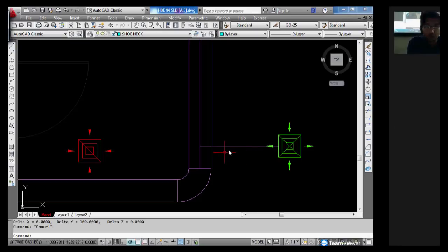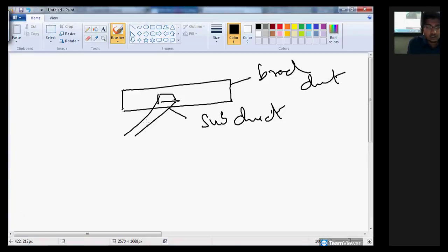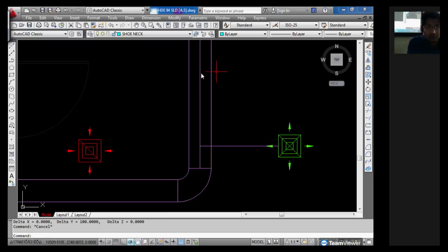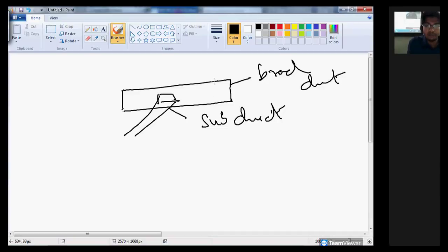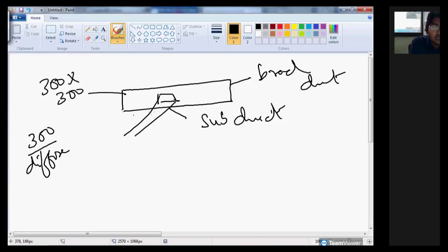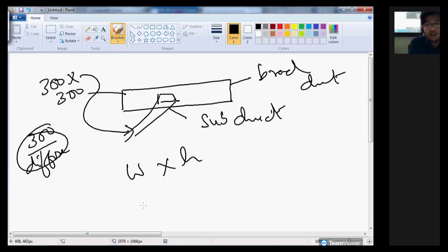Okay, this one that I'm showing here, ये वाला जो है, this is this part. हाँ, this original part is the above one. तो ये उसका section view है जिस तरह से हम लोग देख रहे हैं. अब कभी भी अगर ये duct का size you know it is 300 by 300. Very clear. Now I'm going to apply a sub duct whose neck face is again 300 for the diffuser. तो मेरा duct अगर same 300 by 300 size का रहेगा तो इसमें कैसे fit होगा? It has to reduce in terms of width and in terms of height, right?